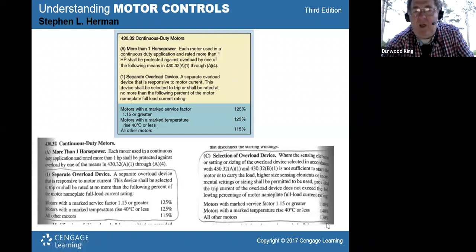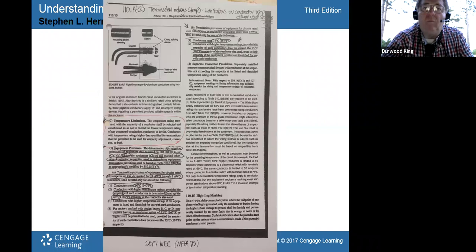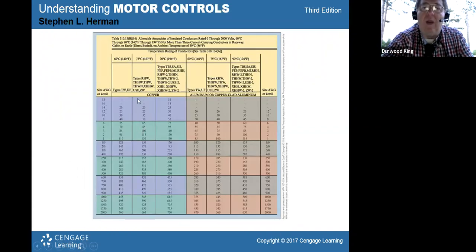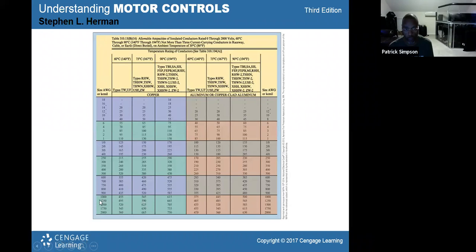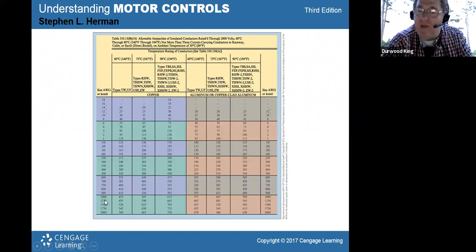My opinion would be you got to use some common sense with this stuff. When you go up in them higher numbers like that, then you need to go back to your wire size and say, well, if you're going to run it at 580 amps, if that's your overload trip setting, then let's go back up to the wire chart. All right, we're in this column here because of the terminal ratings. And so for 580 amps, what wire size does it need to be? 1250. 1250 kcmil. So that changes things, doesn't it?